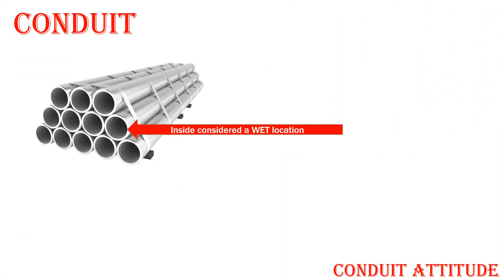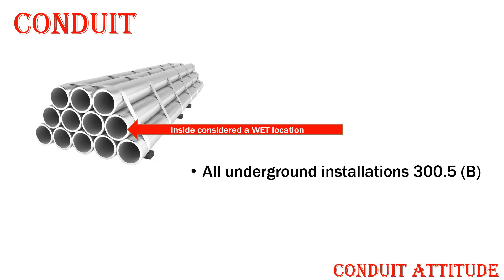There are three major places I want to talk about today where the inside of a conduit is actually considered a wet location. The first place is all underground installations — we're going to find that in NEC 300.5(B). So anytime we're installing conduit underground, it's instantly considered a wet location, and all of the wet location rules apply.